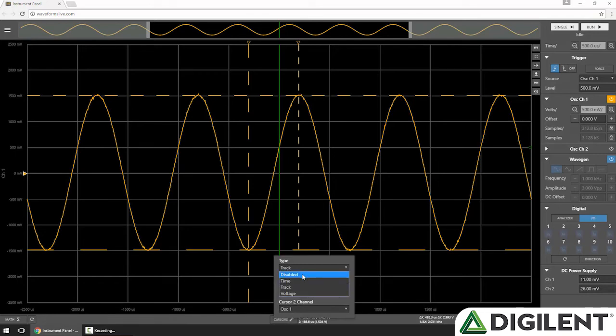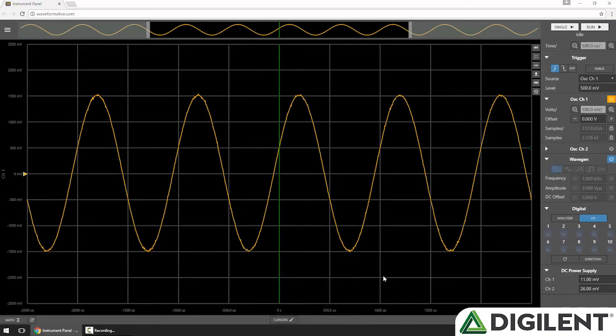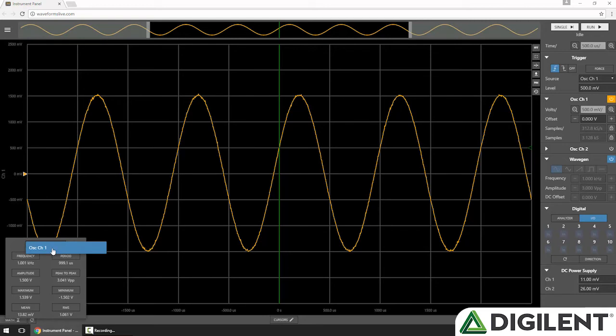I'll switch the cursors back to Disabled to move them off the screen. Now let's look at the math functions. In the lower left, I'll click Math, and first I can pick a channel. Since only channel 1 is enabled, that's my only option here. But if I had channel 2 enabled, I could choose that as well.